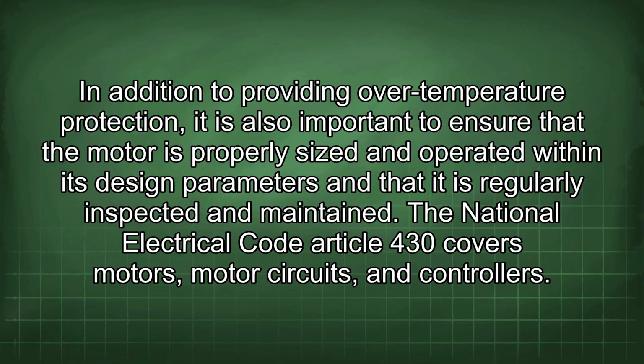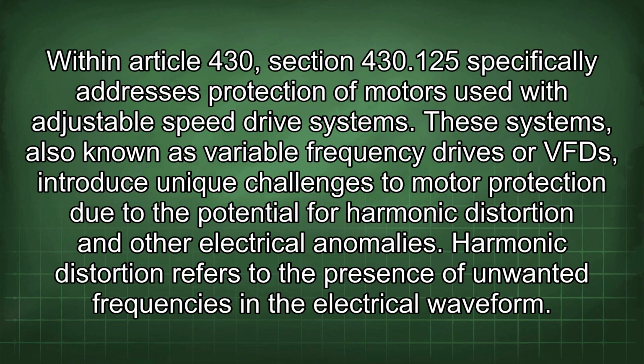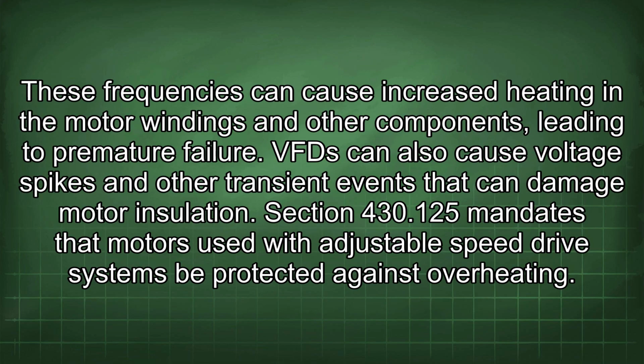The National Electrical Code Article 430 covers motors, motor circuits, and controllers. Within Article 430, Section 430.125 specifically addresses protection of motors used with adjustable speed drive systems. These systems, also known as variable frequency drives or VFDs, introduce unique challenges to motor protection due to the potential for harmonic distortion and other electrical anomalies. Harmonic distortion refers to the presence of unwanted frequencies in the electrical waveform. These frequencies can cause increased heating in the motor windings and other components, leading to premature failure.